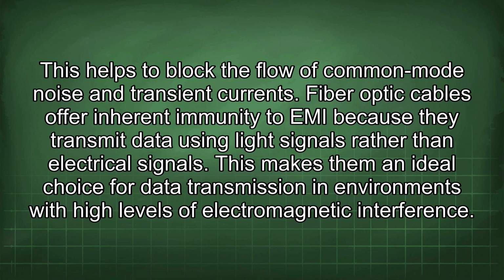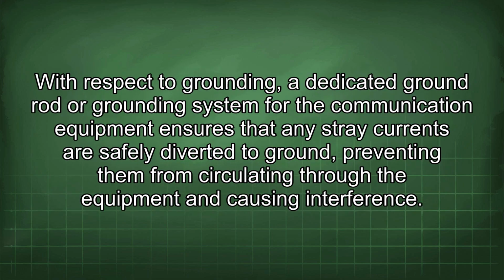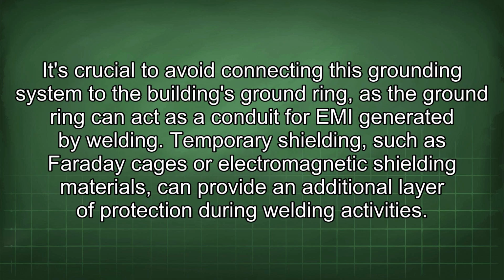Fiber optic cables offer inherent immunity to EMI because they transmit data using light signals rather than electrical signals. This makes them an ideal choice for data transmission in environments with high levels of electromagnetic interference. With respect to grounding, a dedicated ground rod or grounding system for the communication equipment ensures that any stray currents are safely diverted to ground, preventing them from circulating through the equipment and causing interference. It's crucial to avoid connecting this grounding system to the building's ground ring, as the ground ring can act as a conduit for EMI generated by welding.